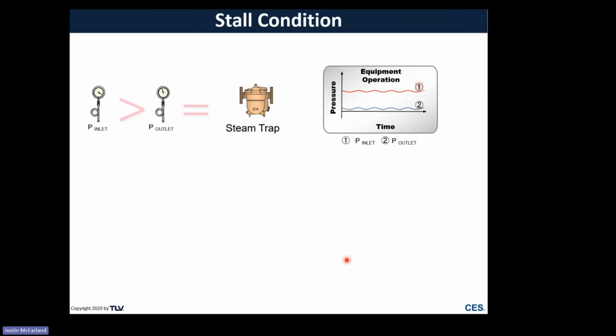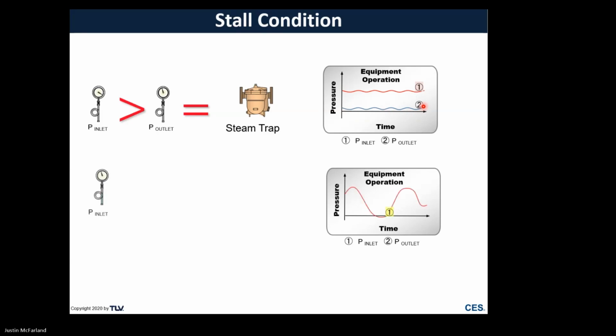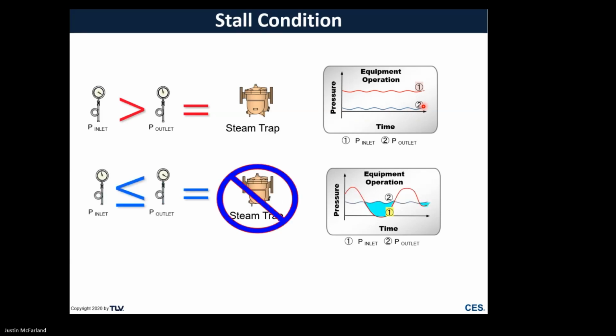So back to using a steam trap. Mention that positive differential pressure is the ideal scenario. You can see a little chart here that over time, that pressure might modulate on the upstream side versus the downstream side, but we always have a positive differential pressure. And if so, then a steam trap is going to work. But if we have some scenario where at times, or all the time, potentially, we have a negative differential scenario, then a steam trap's not going to work. And then we get periods of flooding, and then all those suboptimal symptoms that we had talked about earlier.